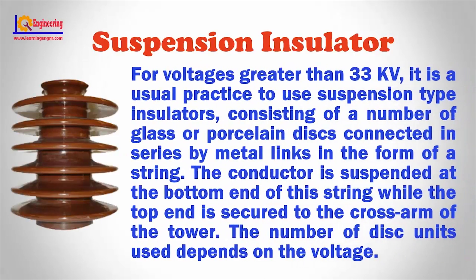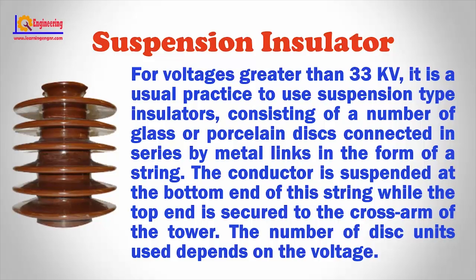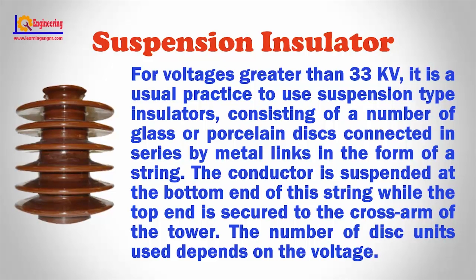Suspension insulator: For voltages greater than 33 kV, it is usual practice to use suspension type insulators, consisting of a number of glass or porcelain disks connected in series by metal links in the form of a string. The conductor is suspended at the bottom end of the string while the top end is secured to the cross arm of the tower. The number of disk units used depends on the voltage.